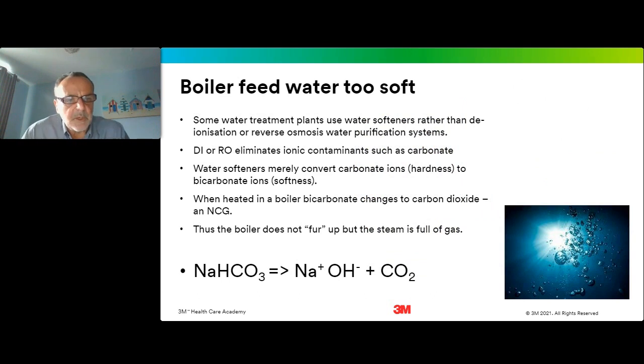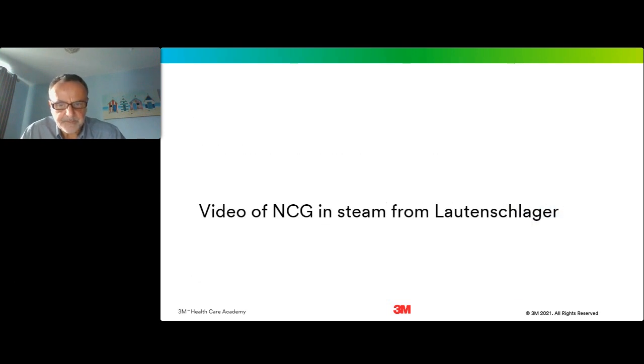Now, softening boiler feed water is a way of removing impurities, but it also can create problems, because it means that calcium and magnesium carbonate salts will be converted to bicarbonate. And as shown in this chemical equation at the bottom, when bicarbonate is heated in the boiler, it will turn into sodium hydroxide and carbon dioxide, which of course is a gas, and that can potentially be carried over in the steam as a non-condensable gas.